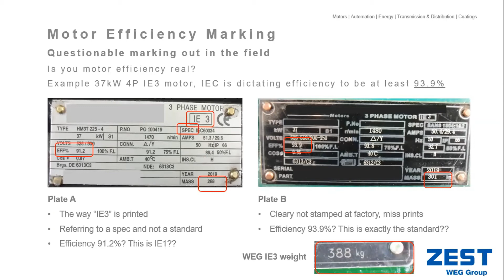If we again look at the rating plate to the right, the darker one, we can clearly see that the information on there is not original equipment. We can see that the engraving on there is not exactly the way it should be. And also, an interesting fact that came out of this nameplate is that the efficiency on this motor is rated at 93.9. And you'll see in my curves later that this is exactly according to the IEC standard. So it is very odd that you'll find an electric motor made that complies to the T with the efficiency rating at 100%. Something else that we also picked up is the weight on these motors: the one on the left indicates a weight of 268 kilograms, the other one 301. And I went and took a picture of our own rating plate, and our motor is rated at 388 kilograms.